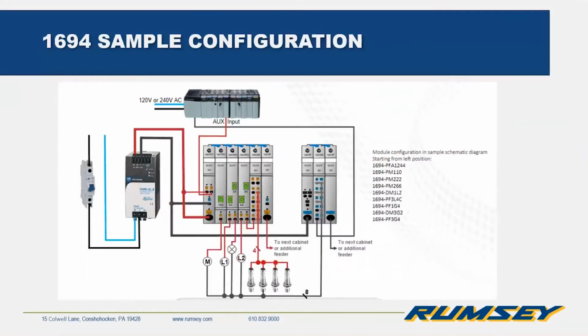And this is really something that's different from any other product on the market right now in terms of its modularity. This slide hopefully illustrates what something like this could help you do. You have your 24-volt coming in off your power supply, being fed into the power feed, going out to the individual loads, which are the four sensors at the bottom. And then you can also have distribution modules to branch this out and scale it. So you could feed a lot of different devices, and it's completely modular. You could set it up however you want, and protect those loads better than you would with either a fuse or a mini circuit breaker, from both short circuits and overloads.